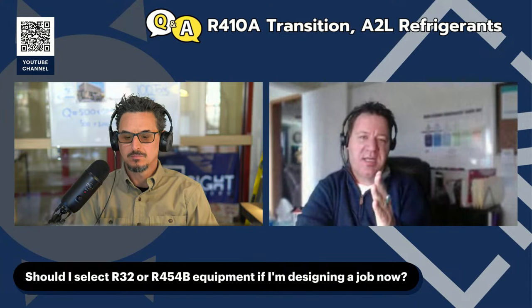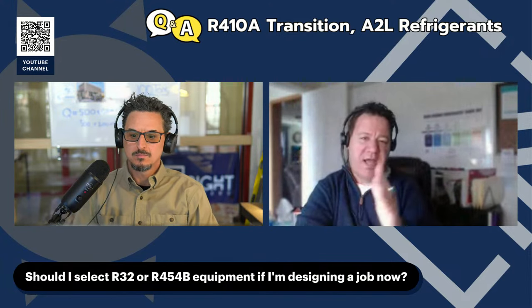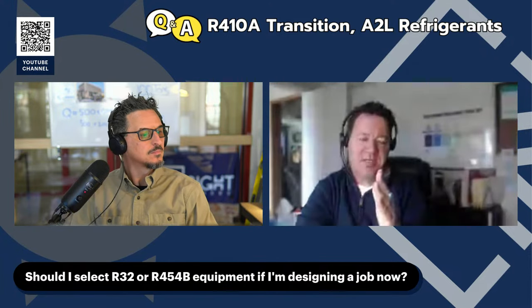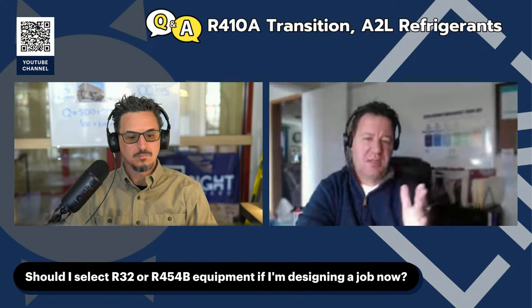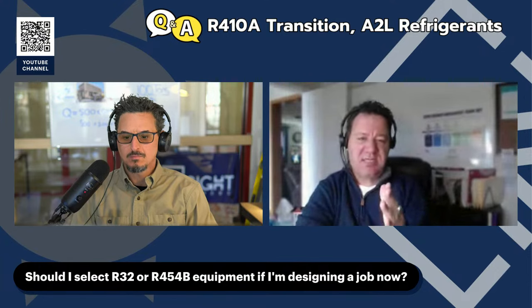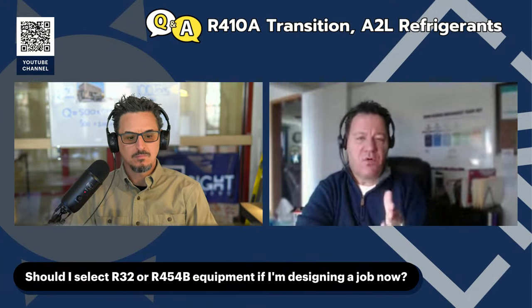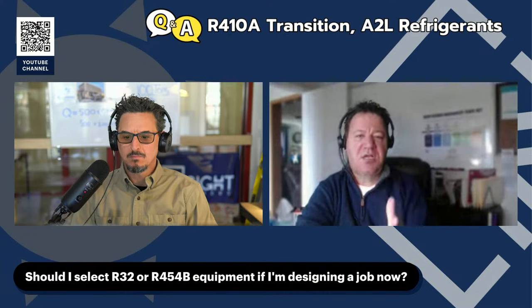Not to get in the weeds, but between an A2L refrigerant and an A2 refrigerant, on the right-hand side of that template are A2s—that flame has to travel greater than 10 centimeters per second. A2Ls are less than 10 centimeters per second. 454B is 5.4 centimeters per second. You can literally walk faster than that flame spreads.